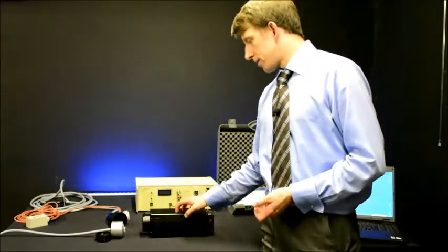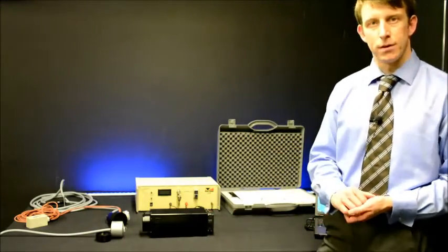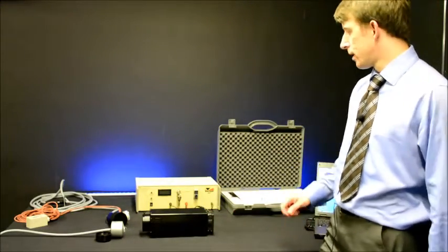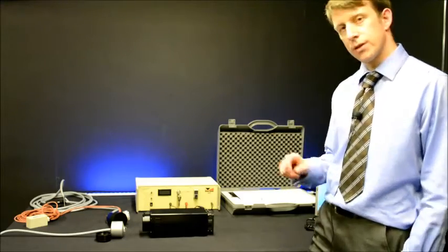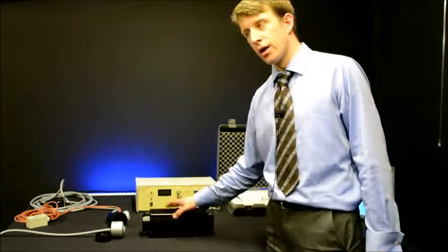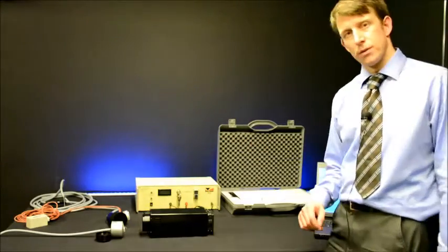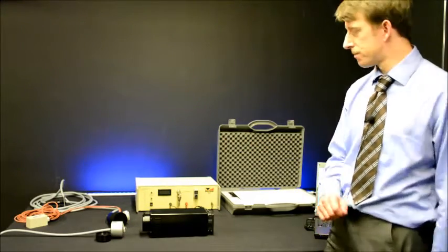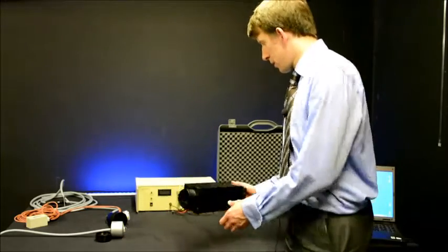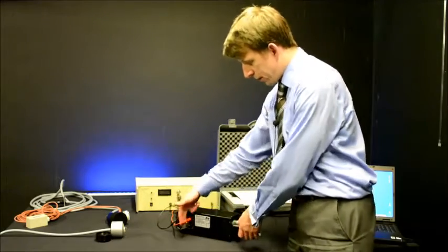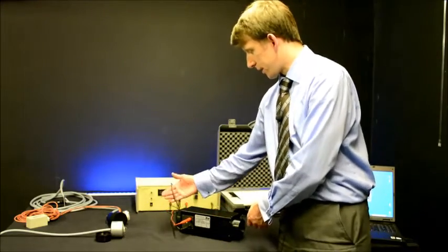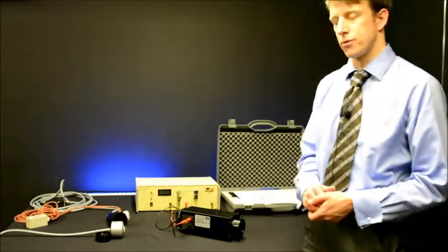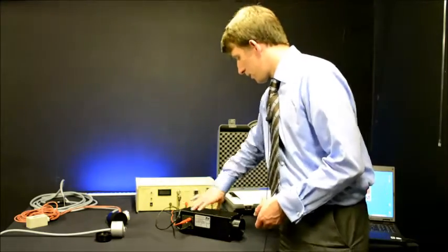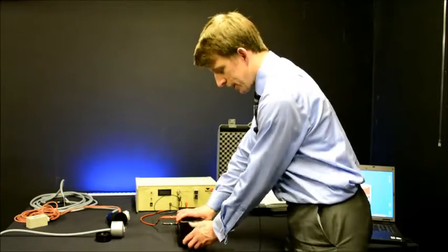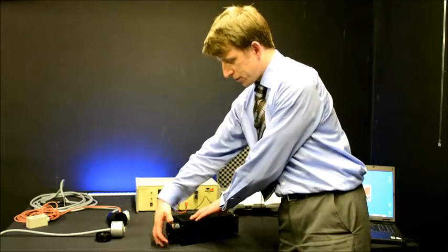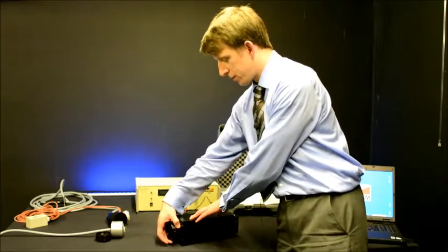The CL6H is operated by the Bentham 605 constant current power supply. One must be very careful that this lamp is operated at 6.3 amps, whereas the other lamp, powered by the same supply, is operated at 8.5 amps. The 605 has red and black inputs and a fan connection to the 605 constant current power supply. The 605 has two adapters which can screw on and off as required.